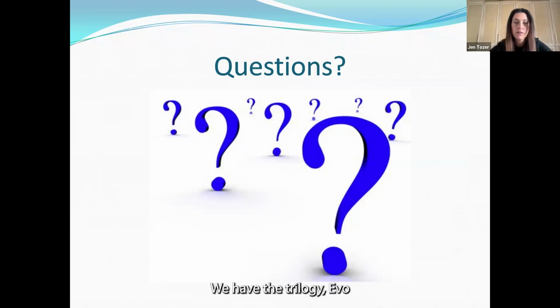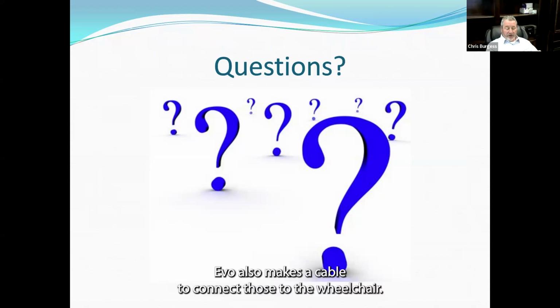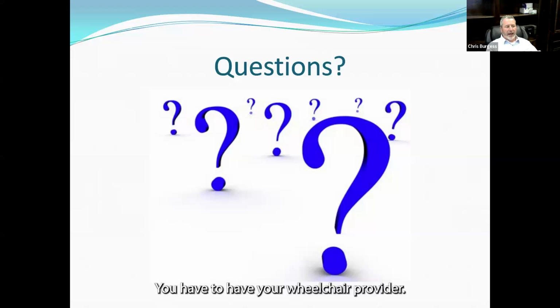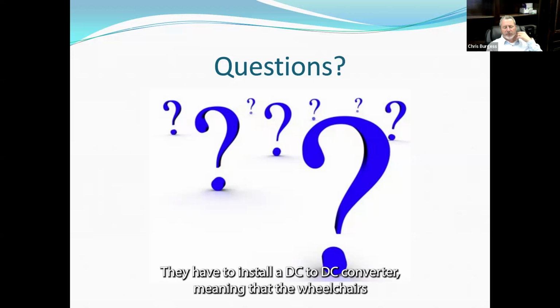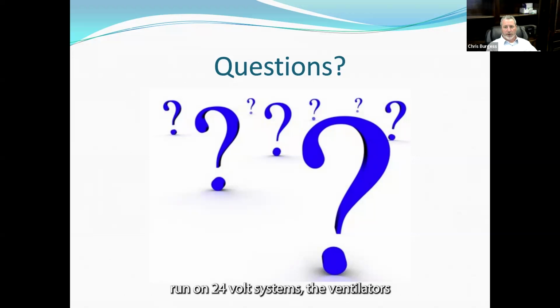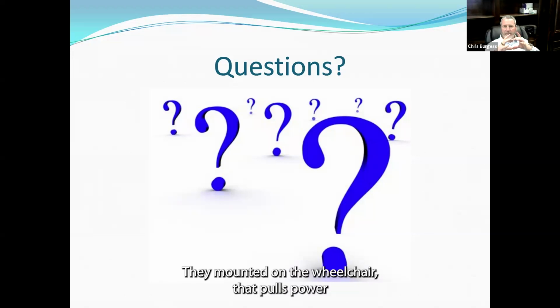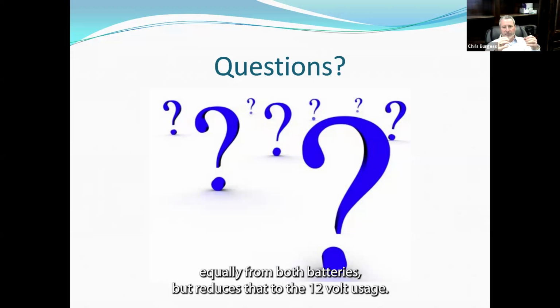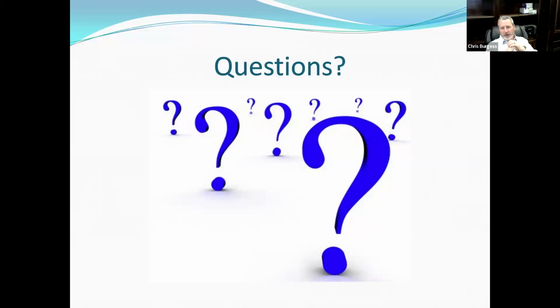We have the Trilogy Evo. Trilogy Evo also makes a cable to connect those to the wheelchair. I think if I remember correctly on the Evo, you have to have your wheelchair provider install a DC to DC converter, meaning that the wheelchairs run on 24-volt systems, the ventilators run on 12-volt systems. So you have to have a small box, they mount it on the wheelchair, that pulls power equally from both batteries, but reduces it to the 12-volt usage. But that can be done.